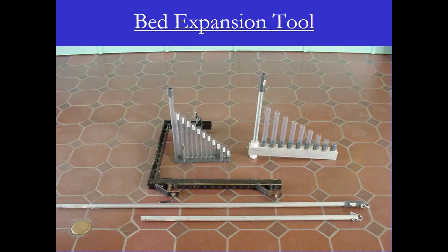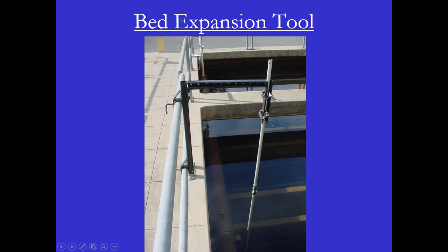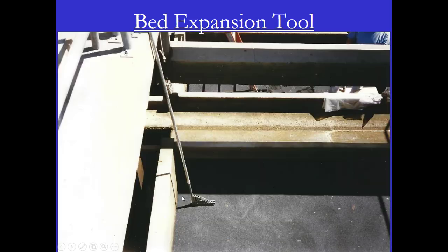This tool is not something you'd go to Home Depot and buy — this is something you'd have to make. This is a bed expansion tool, or a pan pipe — hence Pan Pipe Productions. This tool is a variety of tubes ranging from two inches to 12 inches. What it tests is how much the bed is expanding at the high wash. The bed should expand somewhere between 20 and 30 percent, not typically more than 30 percent. This device is used to hold the bed expansion tool on top of the media during the backwash, and this is the pipe that lowers the bed expansion tool into the filter.